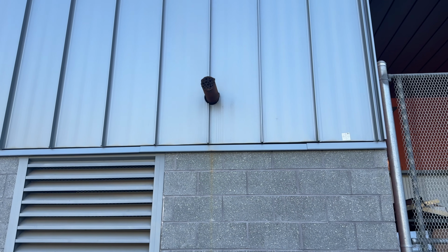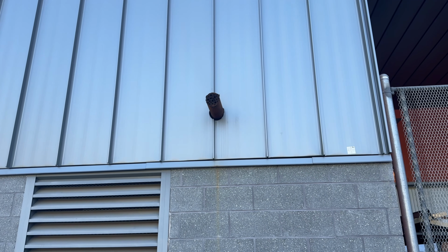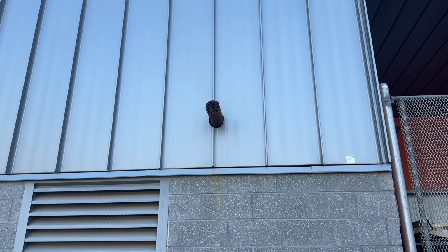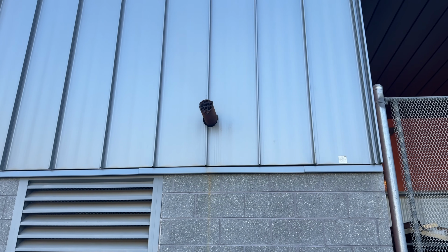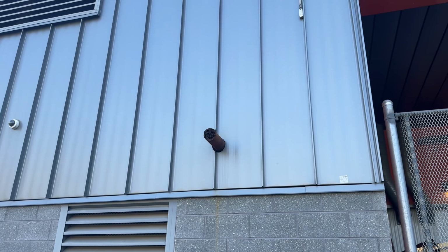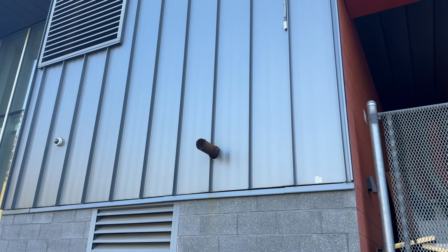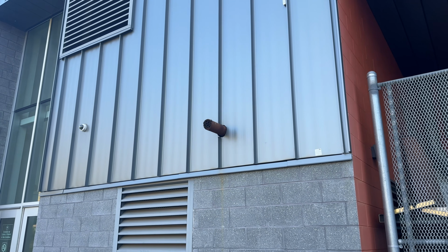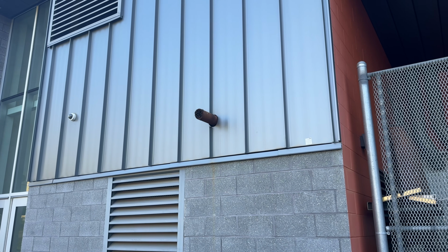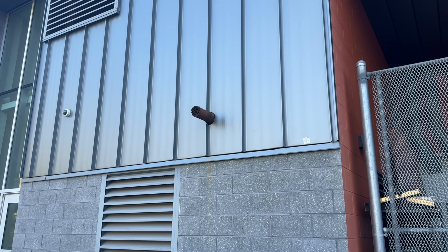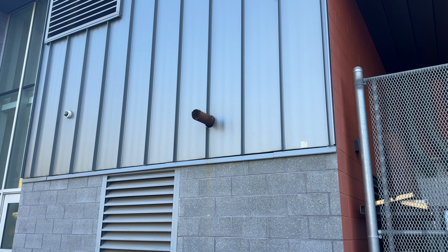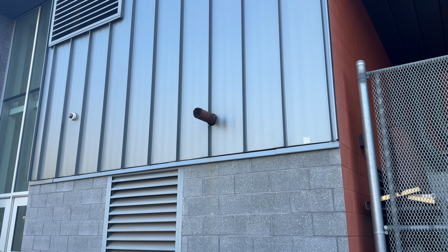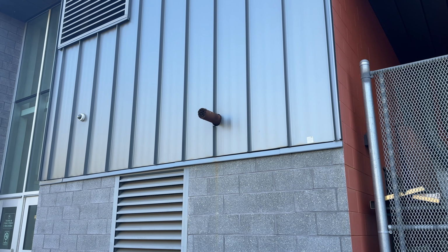It's good for the generator to run for a little bit, get nice and warm. Of course, we're not running it at high amperage, which, I'm not a diesel mechanic, so I can't speak with any knowledge behind this, but people have told me that's when you'll get wet stacking, which I believe is true, when you're running at lesser load. I've also been told modern diesels don't suffer from that as badly.